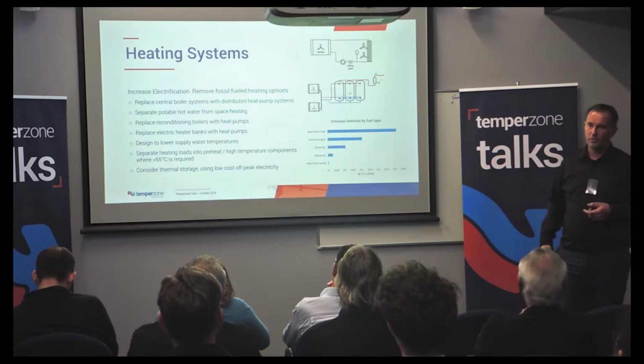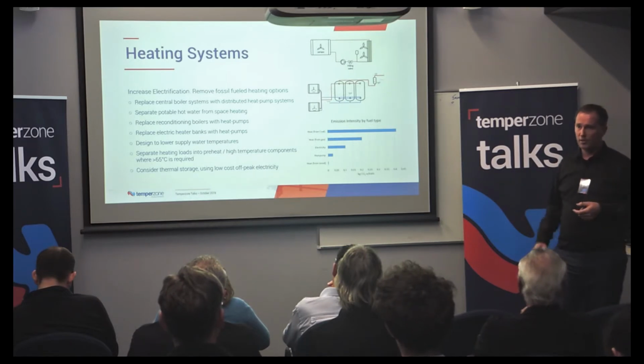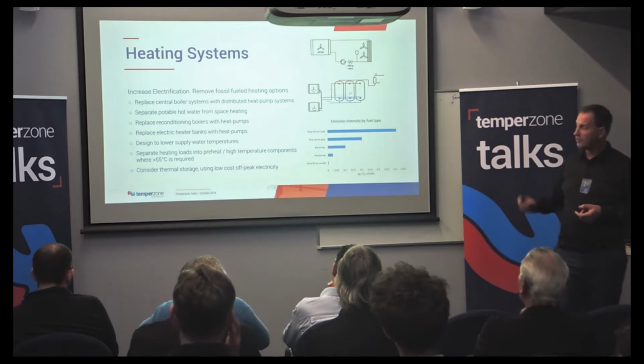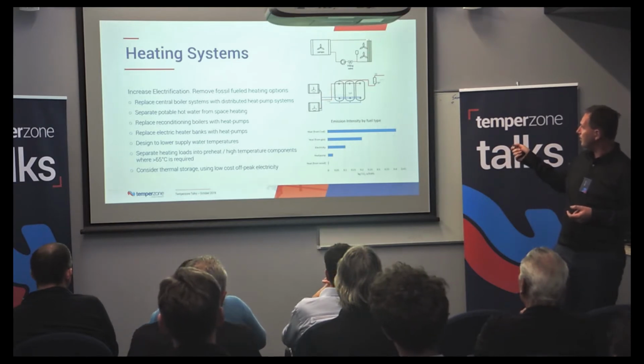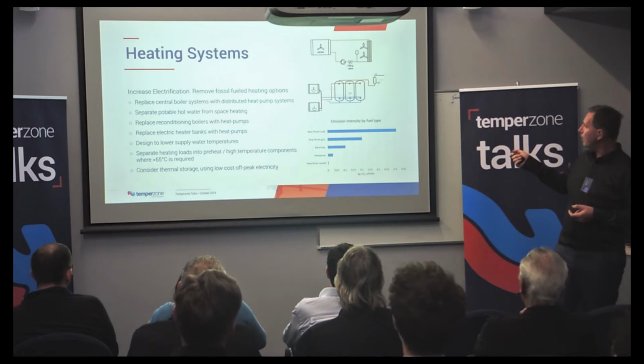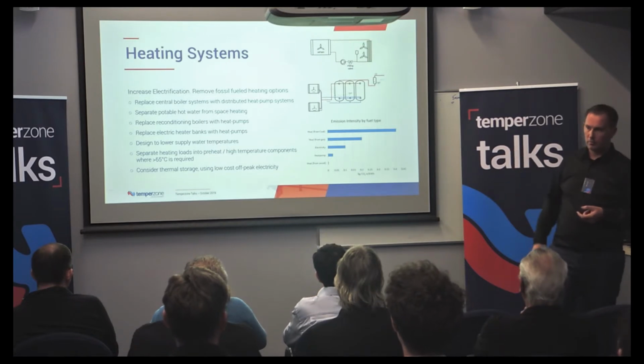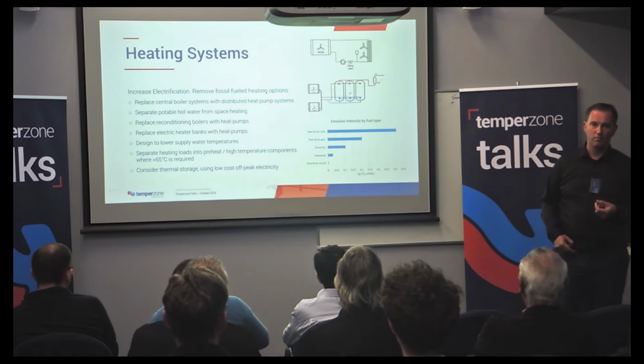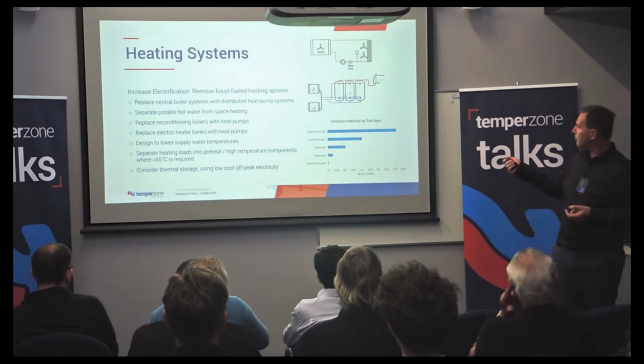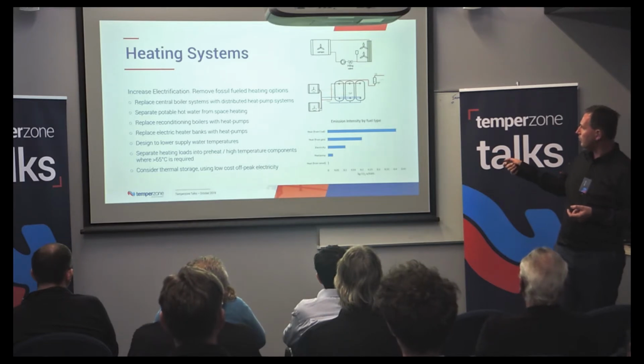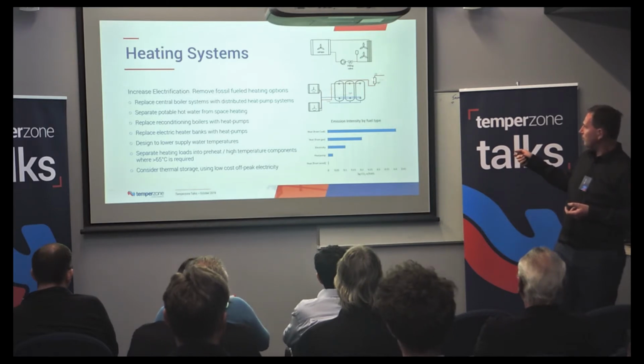Reconditioning boilers on water source units. Gas, usually heat pumps can do the same thing. Electric heater banks, you can use heat pumps, boiler coolers. So this is an example here. This is just an AHU fan coil with an inverter and a heat pump system that will provide the same heat for about a quarter of the electricity. Potable water, like we've got here, multiple tanks, simple pass, top-down heat pumps with a separated main system so that you maintain the thermal stratification of the tanks.